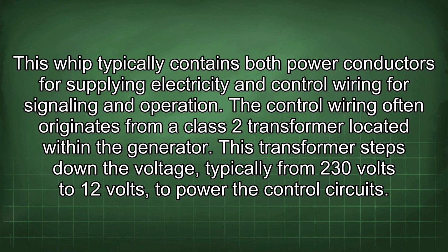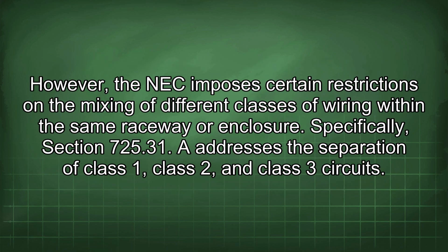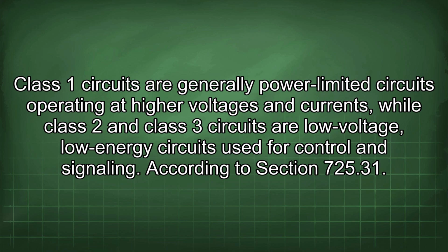The control wiring often originates from a Class 2 transformer located within the generator. This transformer steps down the voltage, typically from 230 volts to 12 volts, to power the control circuits. However, the NEC imposes certain restrictions on the mixing of different classes of wiring within the same raceway or enclosure. Specifically, Section 725.31 addresses the separation of Class 1, Class 2, and Class 3 circuits. Class 1 circuits are generally power-limited circuits operating at higher voltages and currents, while Class 2 and Class 3 circuits are low-voltage, low-energy circuits used for control and signaling.